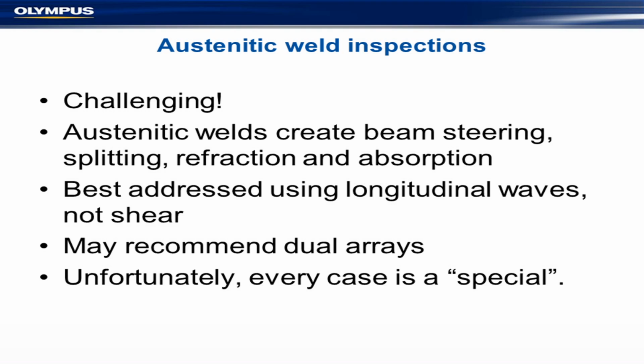The nuclear industry didn't want to use radiography, they wanted to use ultrasonics for a variety of reasons, and ultrasonics really fell badly. So they did some research on this, and they discovered that longitudinal waves were much less affected than shear waves. The shear wave suffered all kinds of problems: beam steering, splitting, refraction, absorption, you name it. We also came up with dual arrays, so there's a transmitter and a receiver. That cleaned up your noise a bit. The problem is that every single case, every weld, is basically a special, so you need to work out your own techniques for that particular weld. The good news is that once you've got your WPS worked out, that will then be pretty much a standard microstructure. So you just get a standardized weld, and off you go. You just side-drill your holes or whatever.